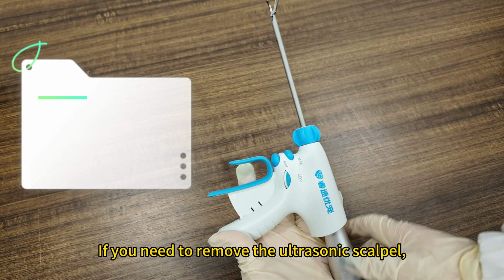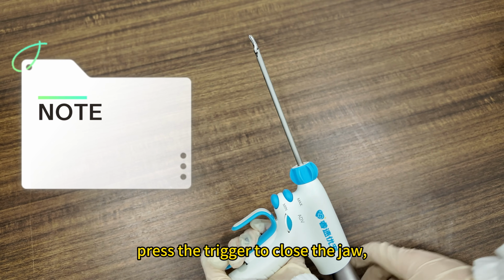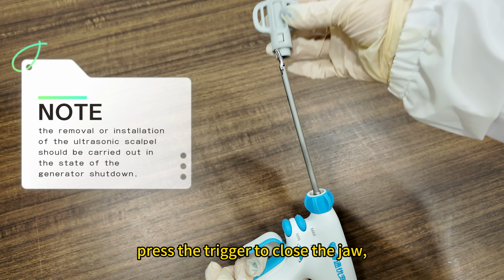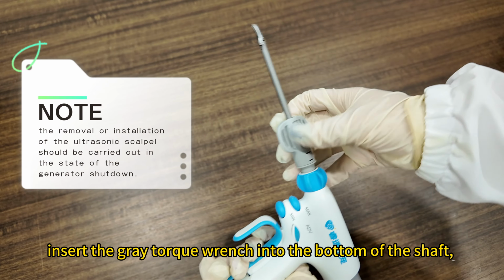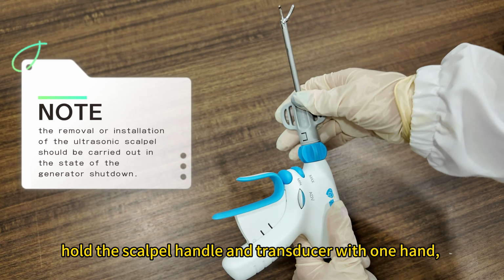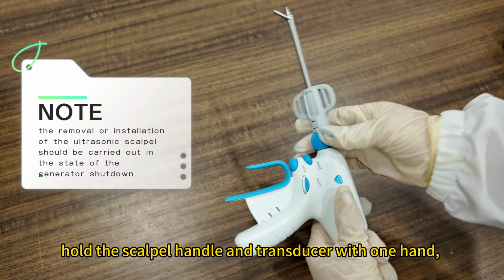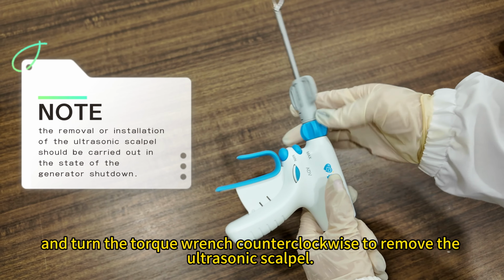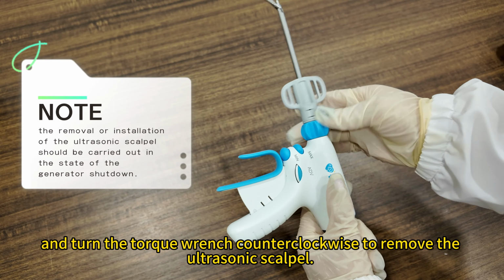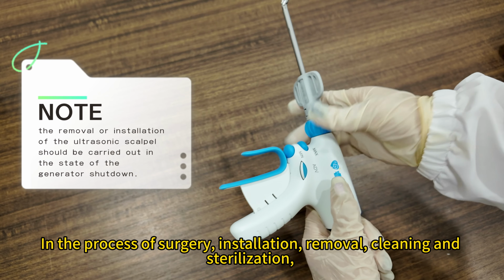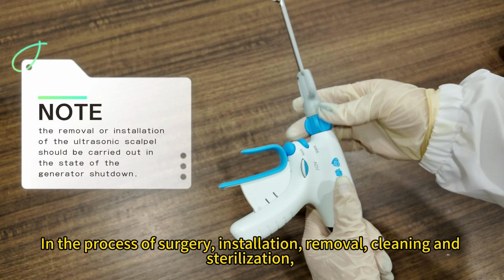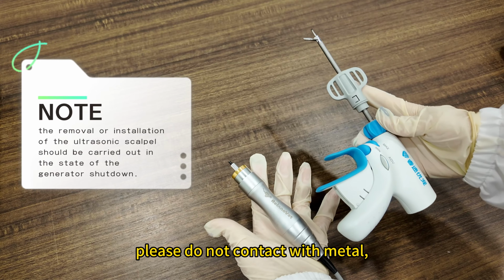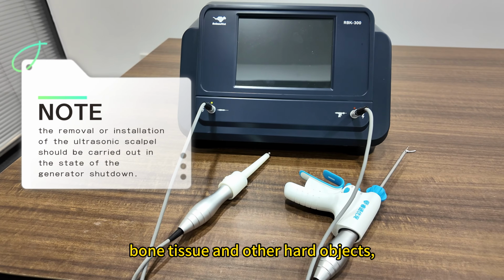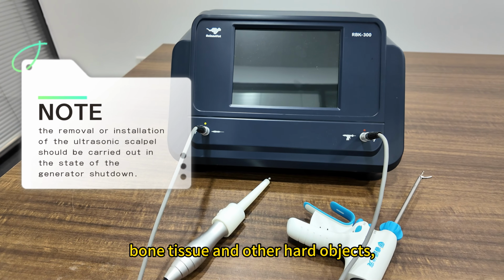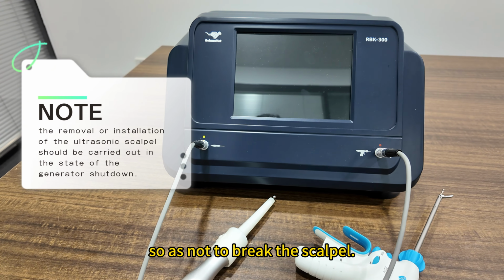If you need to remove the ultrasonic scalpel, press the trigger to close the jaw. Insert the gray torque wrench into the bottom of the shaft. Hold the scalpel handle and transducer with one hand, and turn the torque wrench counterclockwise to remove the ultrasonic scalpel. In the process of surgery, installation, removal, cleaning, and sterilization, please do not contact metal, bone tissue, and other hard objects, so as not to break the scalpel.